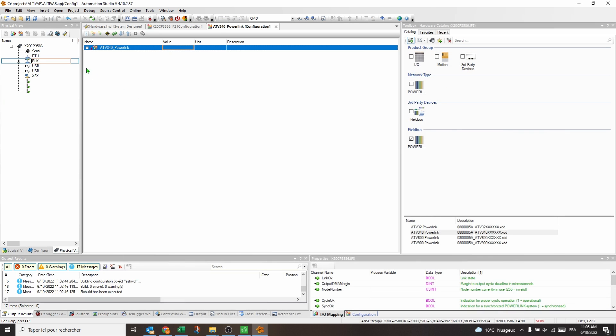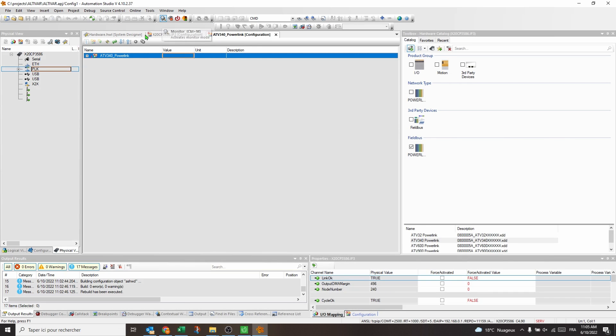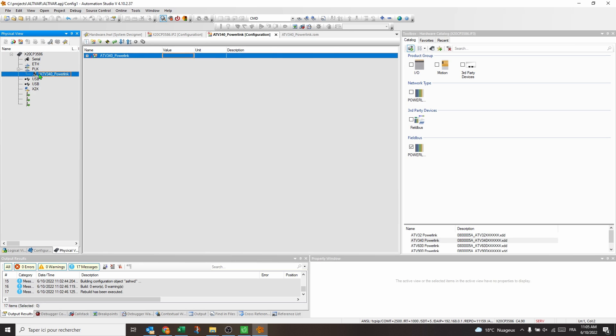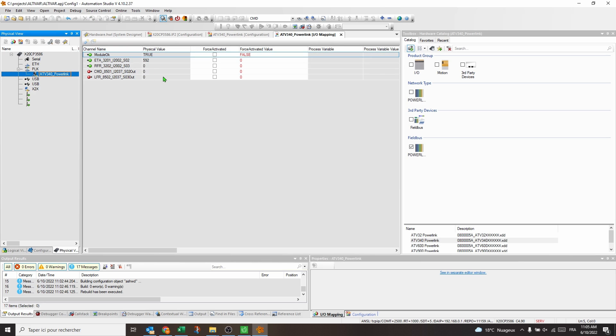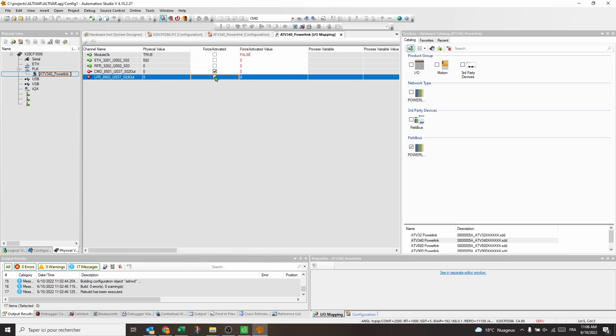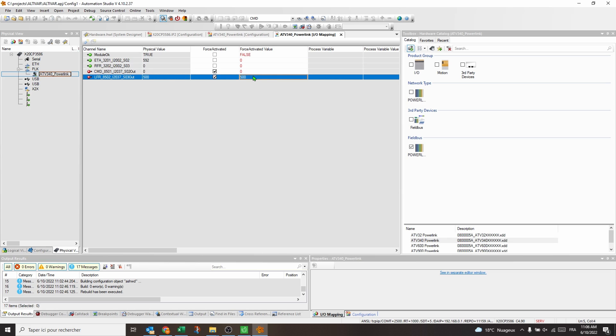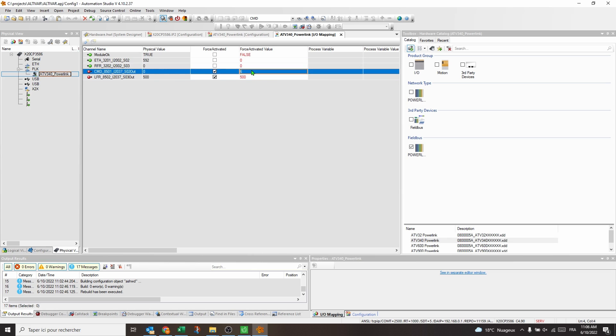In Automation Studio, activate the monitoring and open the I/O mapping of the drive. Module OK shows the status of the communication and ETA shows the drive status. To control the drive, first send the speed reference via LFR in 0.1 Hz. Then send the sequence 6, 7, and 15 via the control word CMD. ETA shows the drive status changing and RFR displays the motor speed in 0.1 Hz.